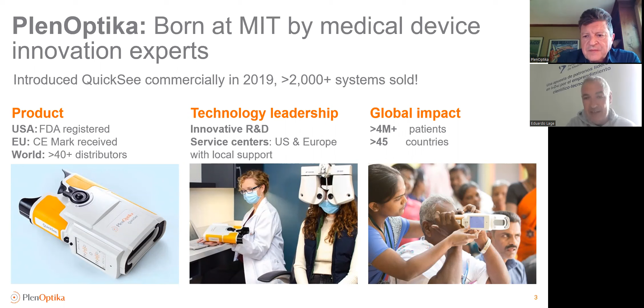What are the basic features of this product? The first thing that I want to call your attention to is that this device doesn't have the typical shape of an auto-refractor or even a portable auto-refractor. We have a binocular form factor, but we can perform binocular or monocular eye measurements. Each measurement takes around 10 seconds, plus the alignment time. The alignment is usually very simple and should not take more than 1 minute. With an experienced user, alignment is immediate. It can take something like 10 seconds.